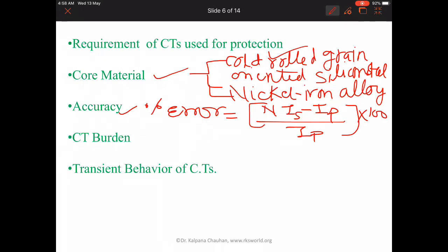The ratio error of a current transformer depends on its exciting current. When the primary current increases, the current transformer tries to produce the corresponding secondary current, and this needs a greater secondary EMF, core flux density, and exciting current. A stage comes when any further increase in primary current is almost absorbed in an increased exciting current, and thereby the secondary current hardly increases at all. At this stage, the current transformer becomes saturated. Thus, the ratio error depends on saturation.